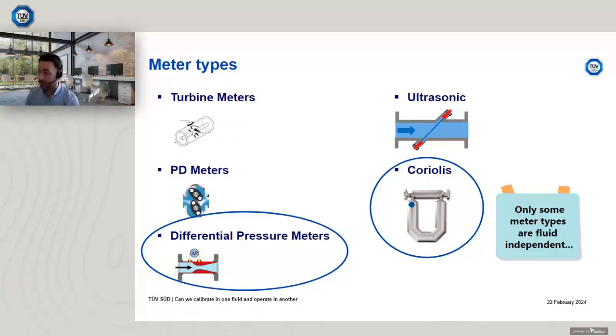So the main point from this slide is that only some meter types are truly fluid independent, such that they can be calibrated in one fluid, be it liquid, and then used in gas, or vice versa. Those two devices I have circled here, so that's differential pressure meters and Coriolis flow meters, and that's where we're focusing the vast majority of our research for this fluid transferability. And some of the results from today's presentation are going to be around Coriolis meters.